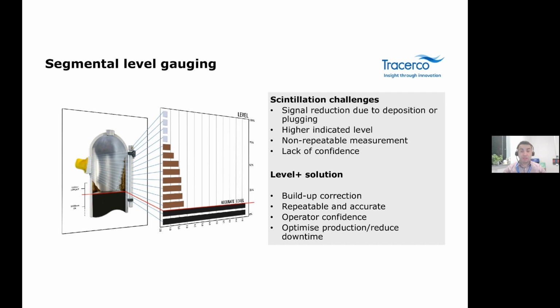For example, varying gas pressure or density in the measurement range can attenuate radiation, reducing the signal and resulting in a higher than actual indicated level. Radiation signal reduces, level increases. That's an example. So our Level Plus solution uses Geiger-Müller tube technology with proprietary software and hardware that can be used for pressure and temperature compensation, with the ability to bring in external pressure inputs or use theoretical pressure compensation. Advanced algorithms in the software are able to overcome the issues mentioned above, including scaling, foaming, and pressure variation.